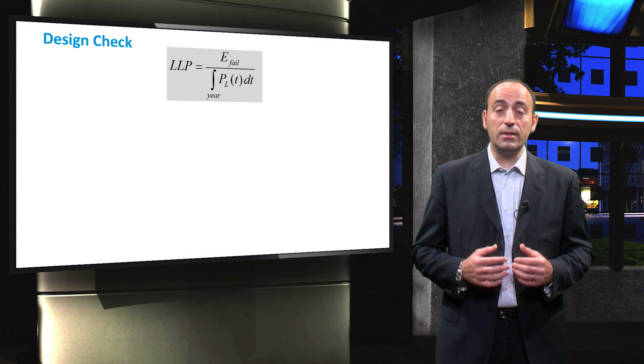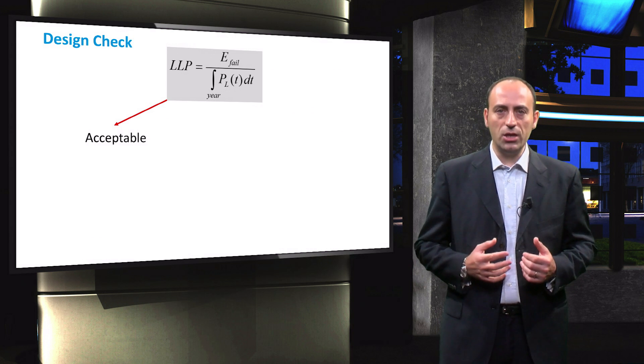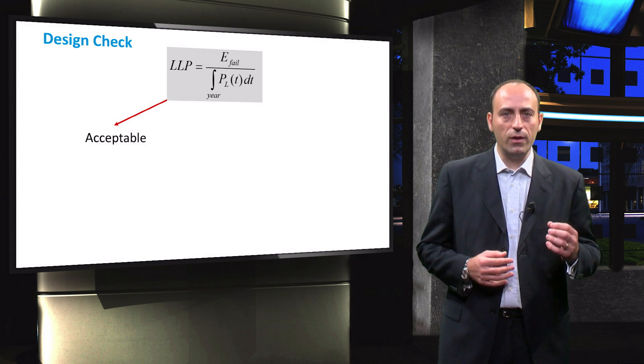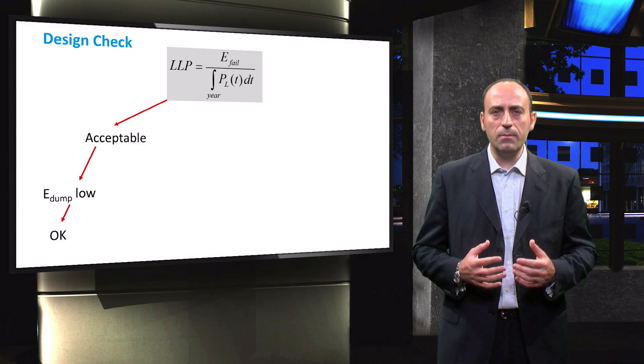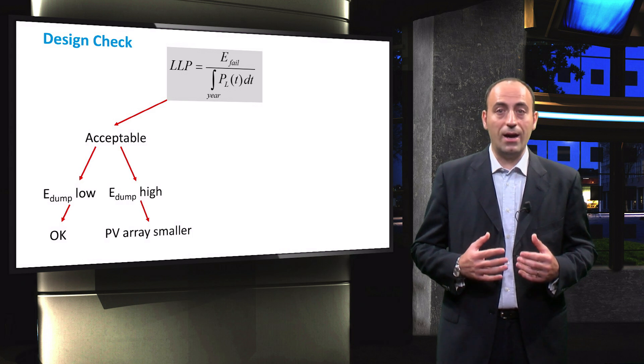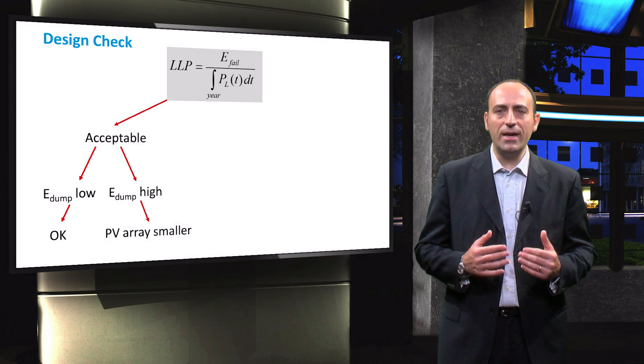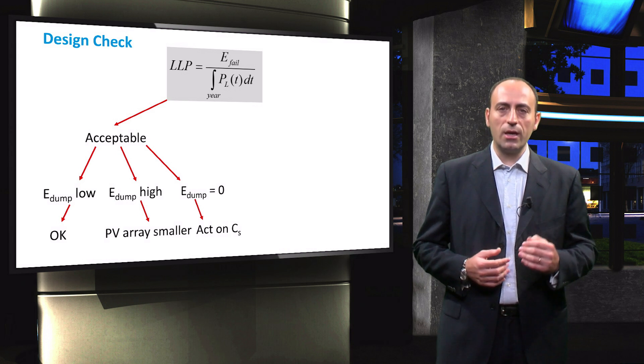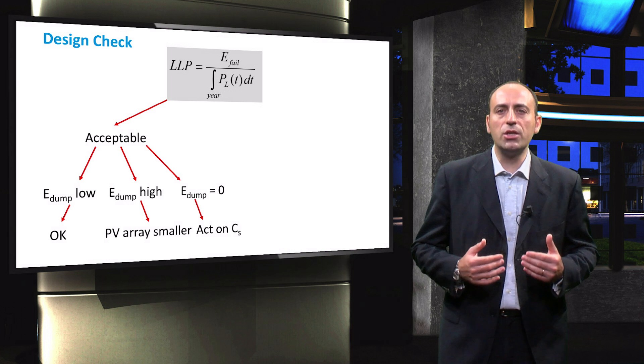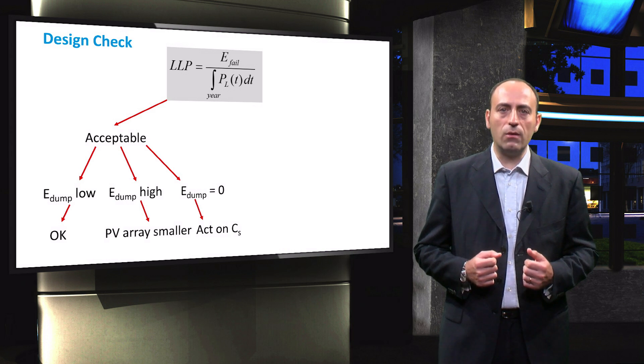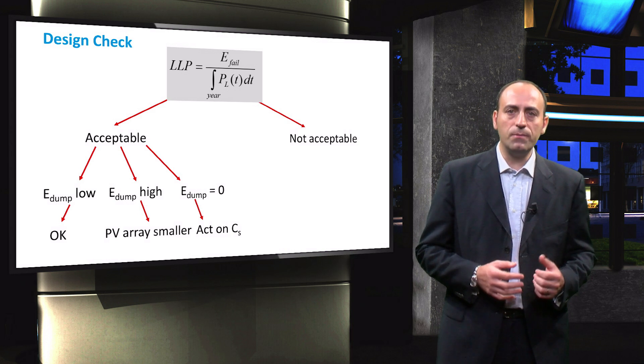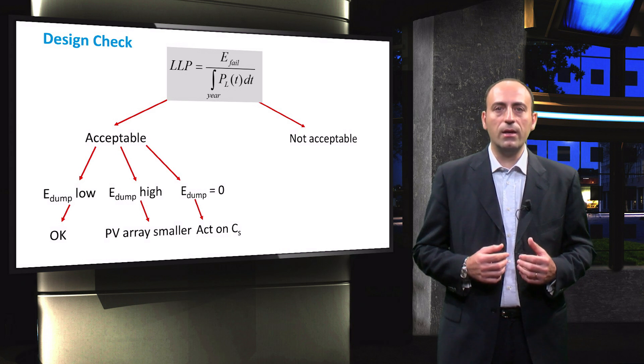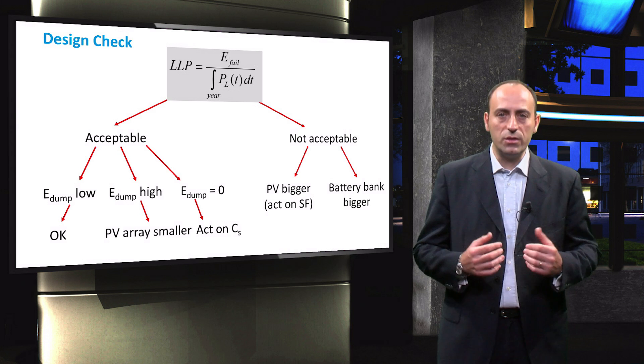If the loss of load probability is acceptable, and this depends on the application of your PV system, the calculated dumped energy by the PV system is assessed. If the E-dump value is low, the system is approved. If the E-dump is high, the PV array sizing is adjusted by downsizing it. And if the E-dump is zero, the number of chosen autonomous days can be reduced. This will potentially reduce the size of the battery bank and eventually bring down the costs involved. On the other hand, if the loss of load probability is not acceptable, either the PV or the battery bank size is adjusted by acting on their corresponding sizing factors.